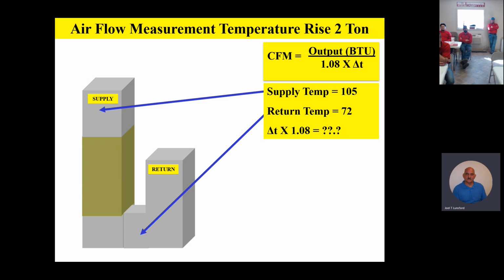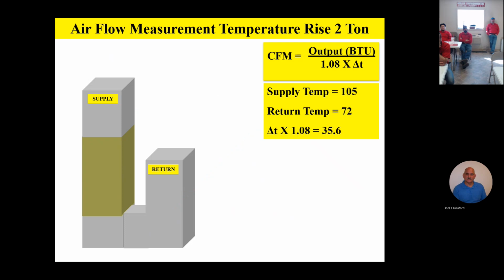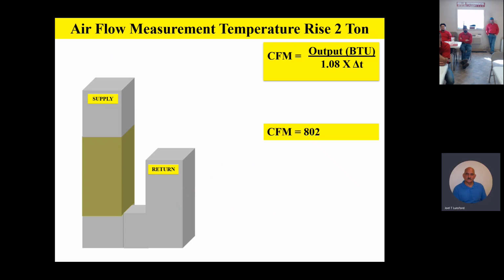And then you take your supply and return air temperature, plug that in with a little bit of math, and get your CFM. So this old temperature rise method is very reliable. It's kind of a backup method. We really want you using the airflow charts, but I just wanted to toss this out at you, that this airflow measurement can also be done with an amp probe, a voltmeter and a temperature probe. That's how we used to do it in the old days. Who's ever used this temperature rise method?